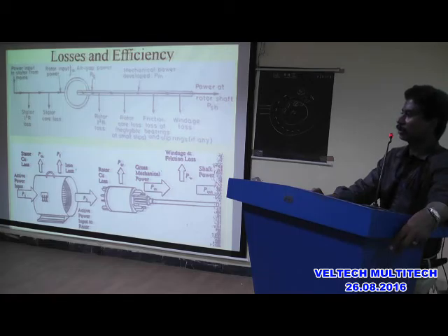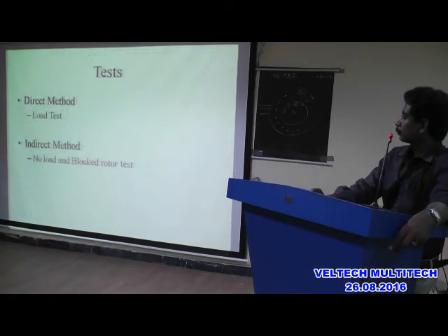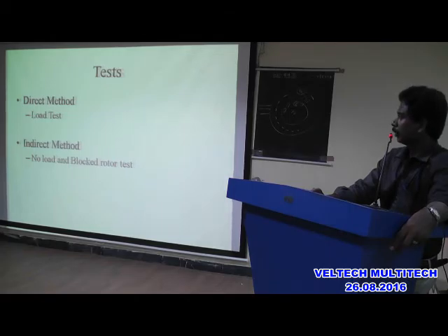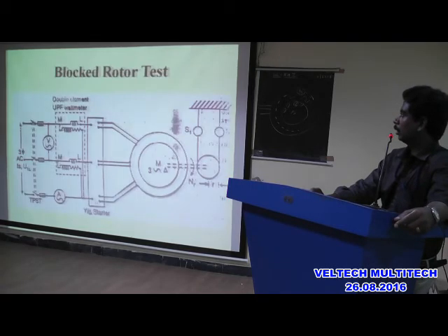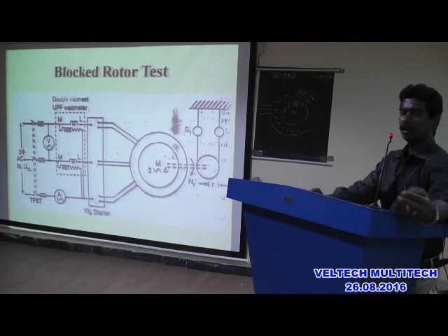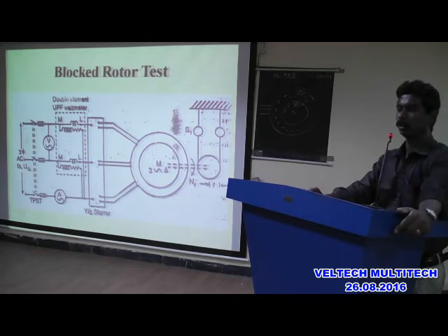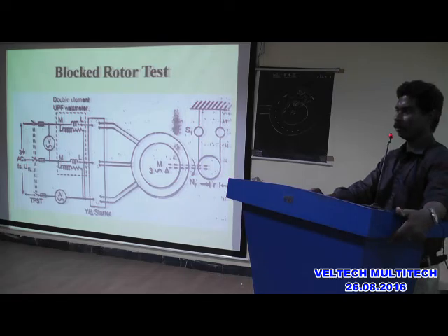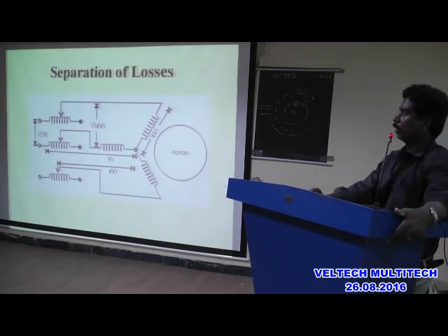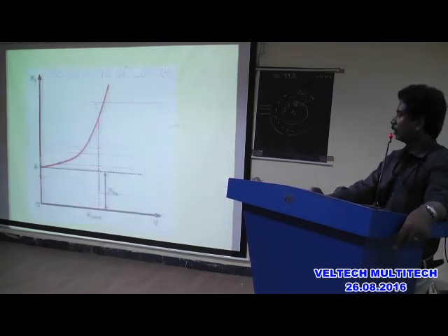Then you know the losses of the induction motor. Then similarly load test, that is direct method, and indirect method, no load and blocked rotor test. Know the testing arrangement, load test. Then no load test, blocked rotor test. Okay, this no load and blocked rotor test are used to determine the equivalent circuit constants of the induction motor. From that you can even calculate the efficiency.